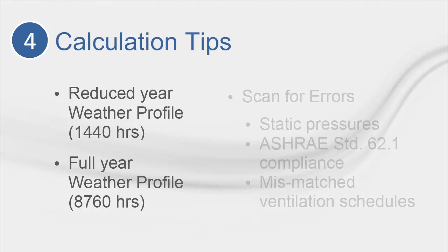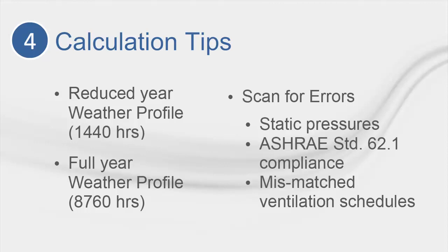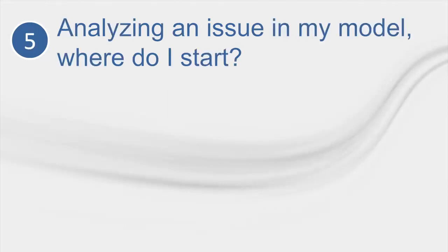Next, use the Scan for Errors button. This will provide a good high-level check for the most basic data entry mistakes. It can tell you if you have forgotten to input static pressure on a fan or if you have applied ASHRAE Standard 62.1 at the room level but have forgotten to turn it on at the system level. The best part, though, is that it happens before you calculate and only takes a few seconds.